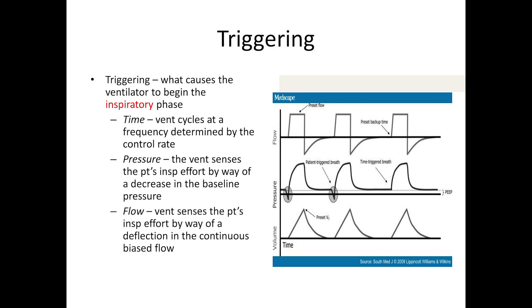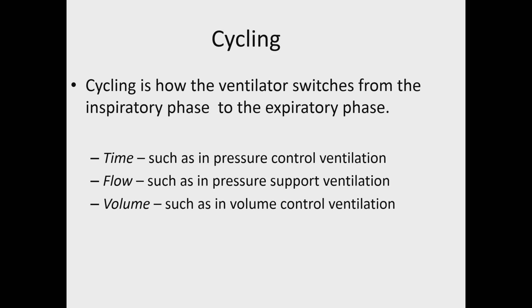The ventilator can also be triggered by pressure. If the patient initiates a breath and there's a negative pressure deflection, that can be sensed by the ventilator to trigger the beginning of inspiration. Similarly, it can be a flow trigger — if the patient begins to take a breath and the ventilator senses that inspiratory effort by way of a deflection in flow, then it will initiate the inspiratory phase.